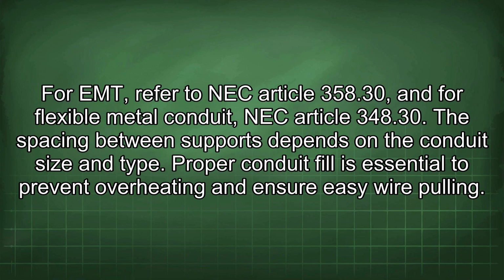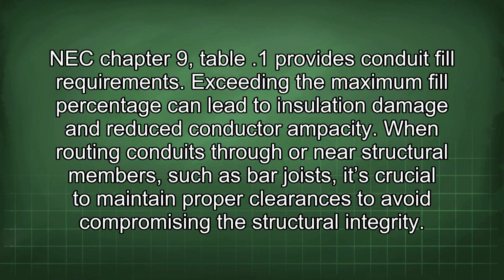Proper conduit fill is essential to prevent overheating and ensure easy wire pulling. NEC Chapter 9 Table 1 provides conduit fill requirements. Exceeding the maximum fill percentage can lead to insulation damage and reduce conductor ampacity.